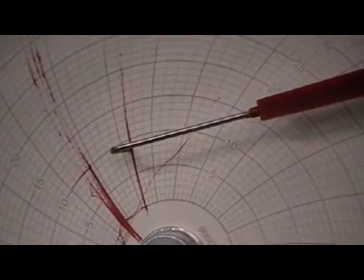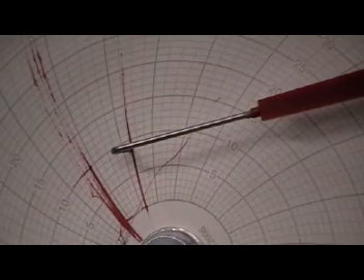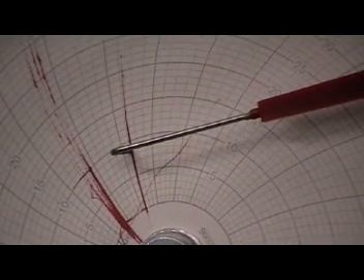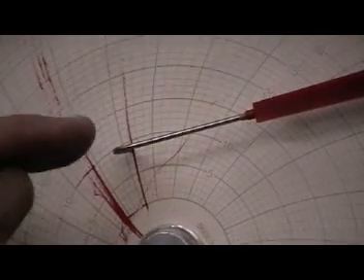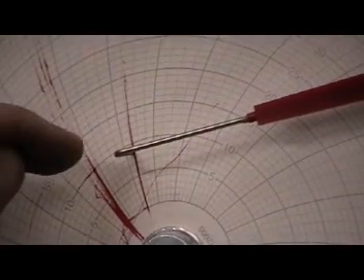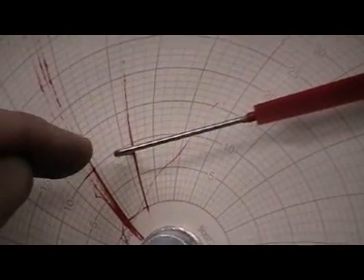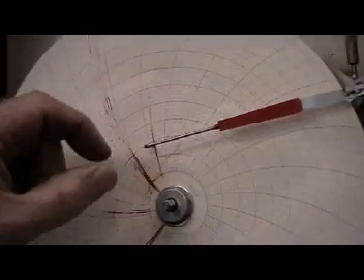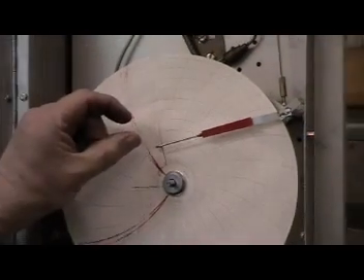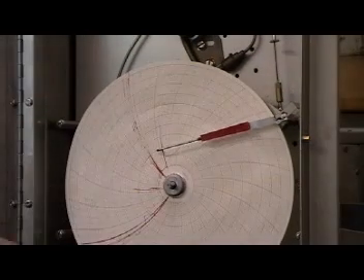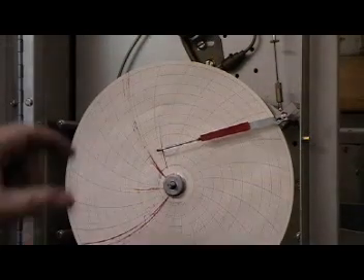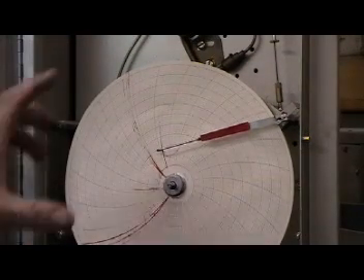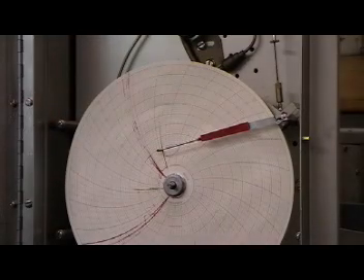Now, for it to be 50 psi that only allows a maximum deviation of half a division above and half a division below if you were going to combine the two. Or one division as a total division somewhere in the chart.